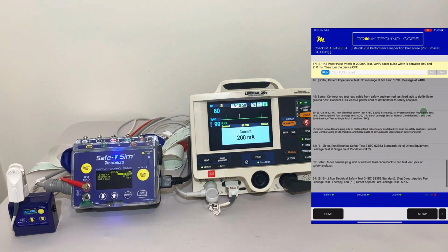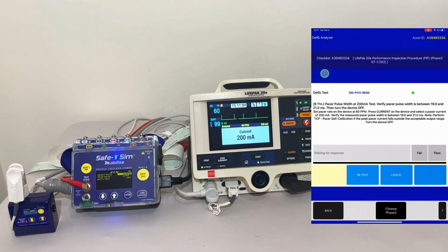We want to make sure the pulse width of the pacing signal itself is within specification. We'll run that test. It's going to measure that pulse width in just a moment here and report back. So we left the current at 200 milliamps, but our pulse width should be between 19 and 21 milliseconds. And you can see here it is 20.26, within range. That is a pass.